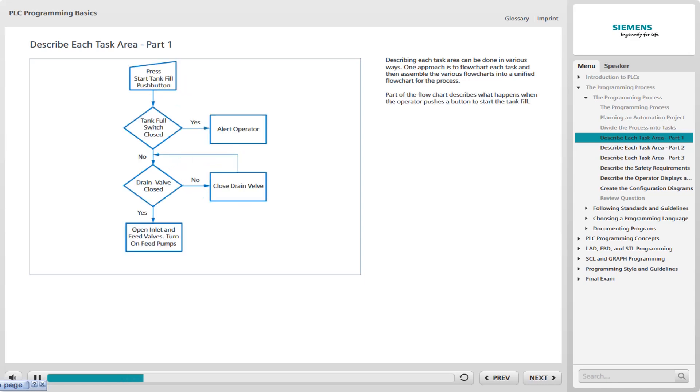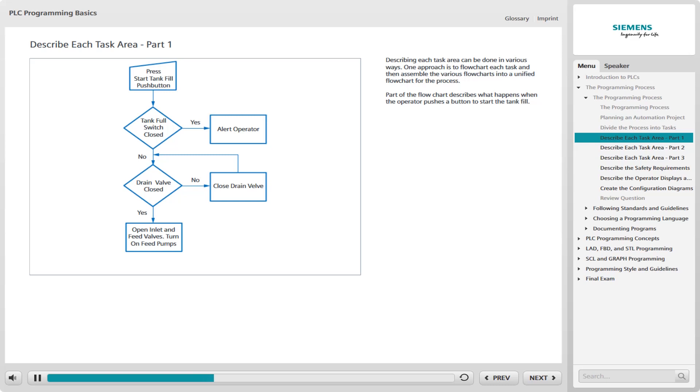Part of the flowchart describes what happens when the operator pushes a button to start the tank fill. This part of the chart identifies the conditions necessary to cause the inlet and feed valves to open and the feed pumps to turn on. It also shows what happens when some of those conditions are not met. There may be additional conditions beyond those shown in the accompanying graphic because this is only a simplified example.